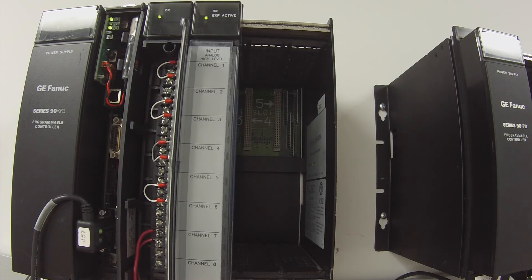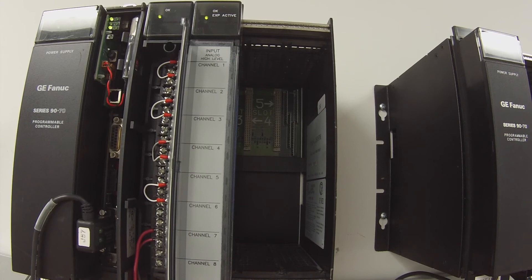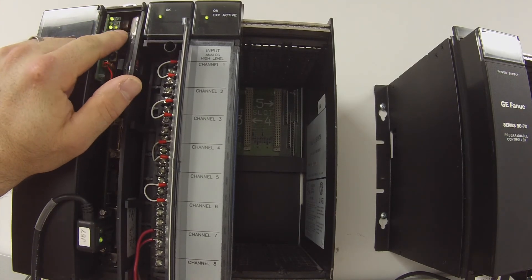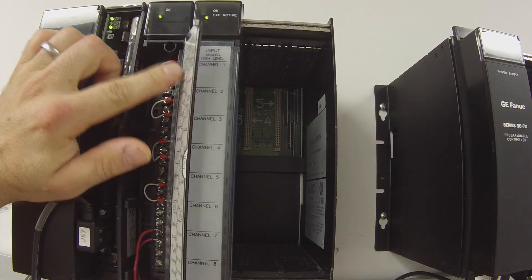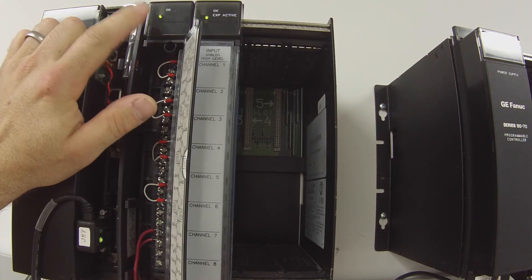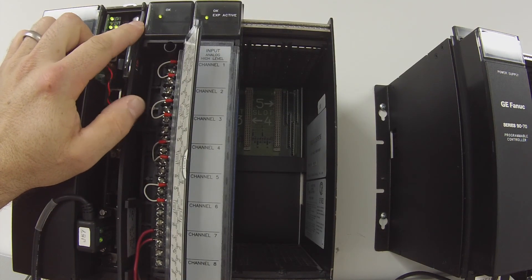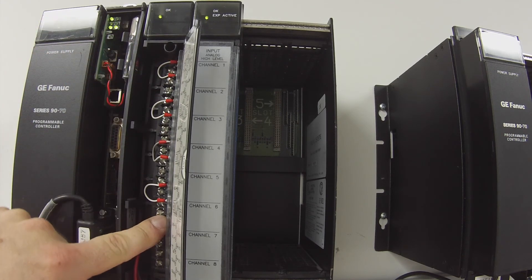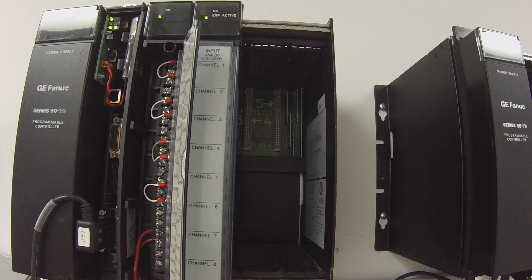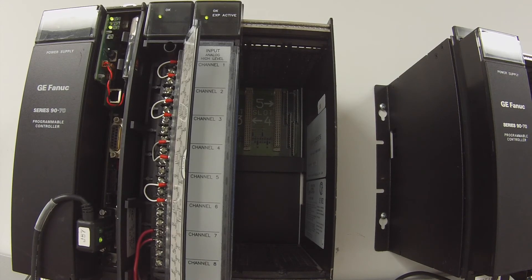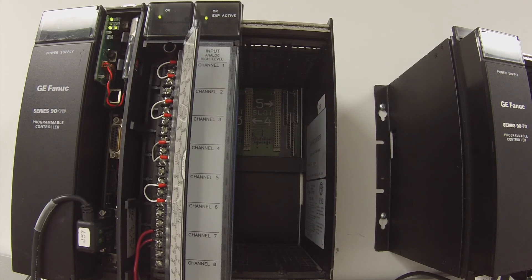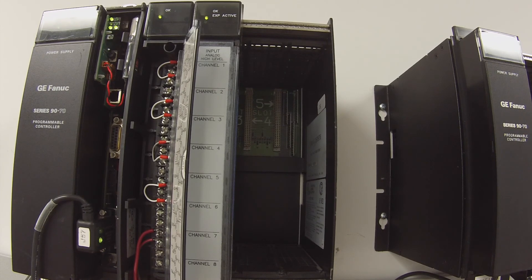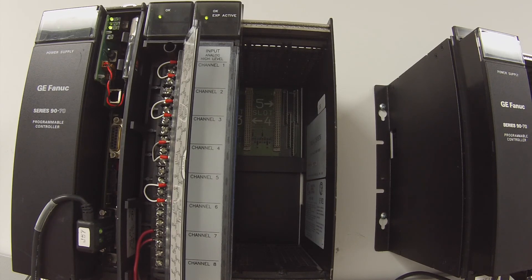I've had situations where the okay light isn't on, but it comes on once it's configured. It's not something you always go by with the okay light, although you should typically have it on. These channels we just went over, voltage 0 to 10 volts and milliamps, you should get readings just like the ones I saw. You should be at 9.99 to 10 volts. You should keep cutting those values in half to make sure it's able to put out that different voltage.